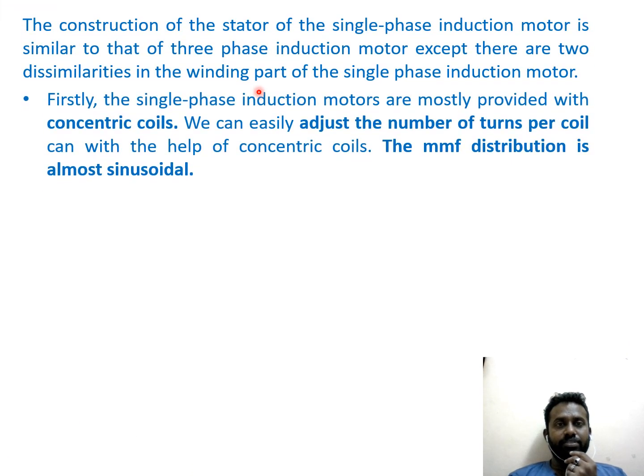The construction of the stator of a single phase induction motor is similar to that of a three phase induction motor, except that there are two dissimilarities in the winding part. Firstly, single phase induction motors are mostly provided with concentric coils. We can easily adjust the number of turns per coil with the help of these concentric coils. The MMF distribution is almost sinusoidal.